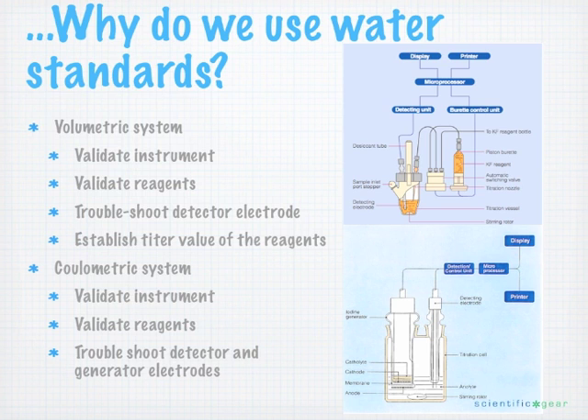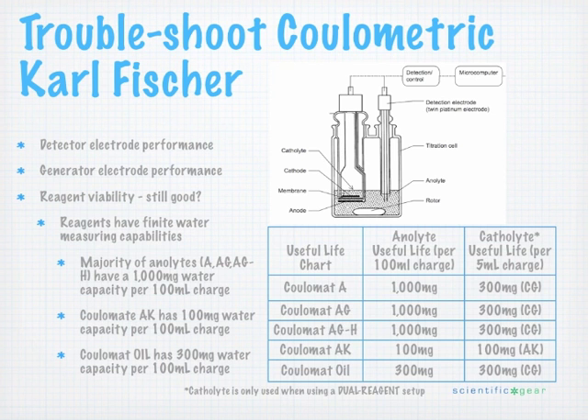On the coulometric side, because it is considered an absolute method, it will always generate the same amount of iodine, provided the reagents are not exhausted. We still need to make sure everything is working properly — a sample may coat the generator electrode or detector electrode. Running a standard can reveal such problems and confirm reagents are still viable. Most coulometric analytes have a 1,000 milligram water capacity per 100 mL charge, except Coulomat AK, which has 100 milligrams, and Coulomat Oil, which has 300 milligrams per 100 mL charge.